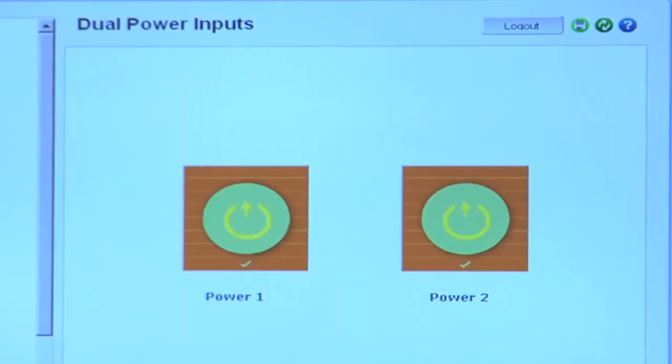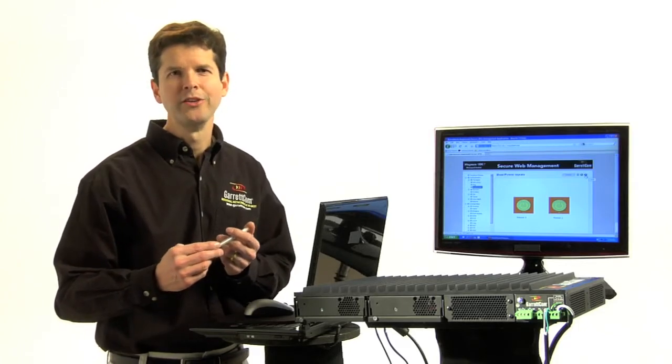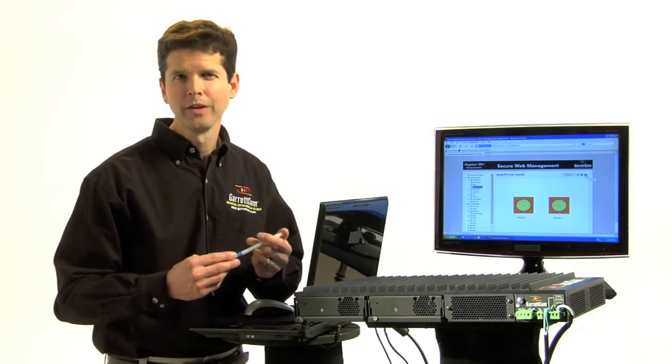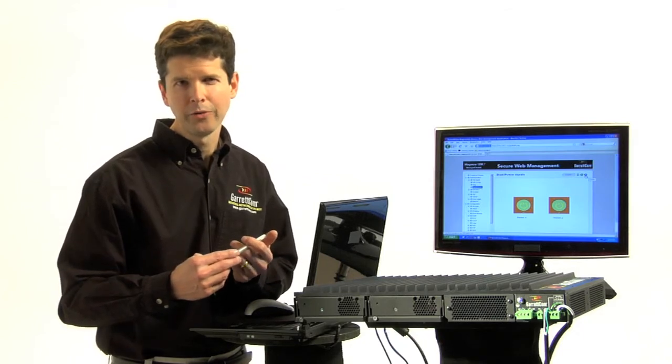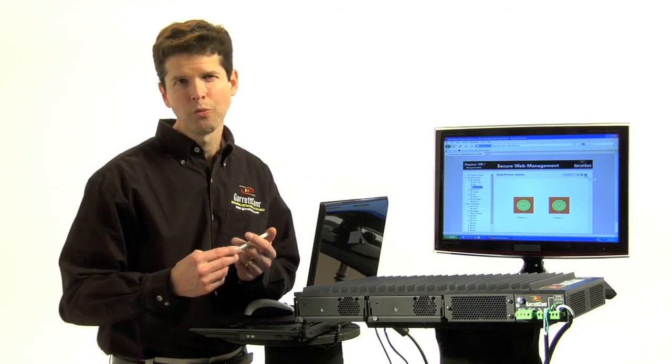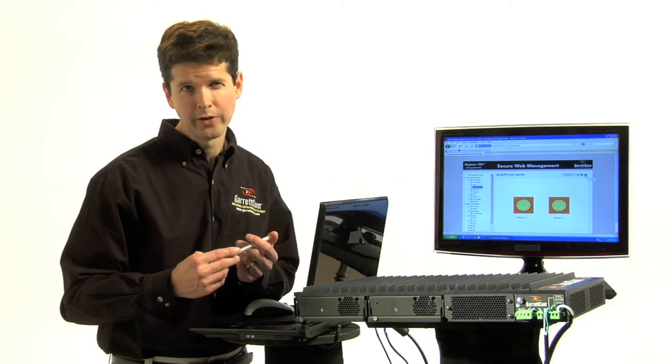So, if you look at it, both of the power supplies, they're up and running, and they're up with redundancy. There has been no network downtime while one of the power supplies was down, and none while the replacement power supply was inserted.